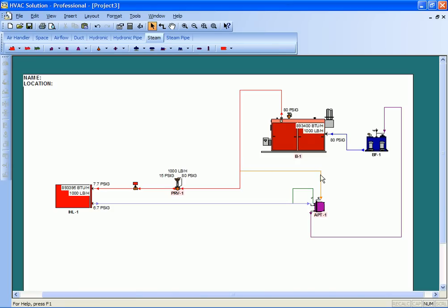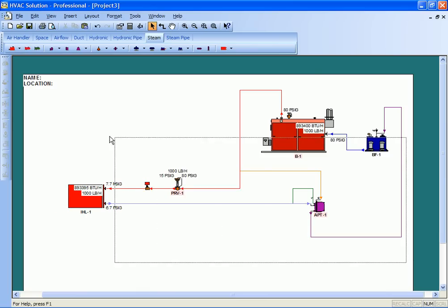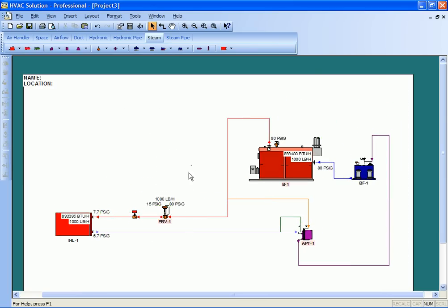So here we just take that 100 psi or say 80 psi steam, use that to power whatever condensate we're coming back, and now this system will function correctly. It won't have any problems because the condensate can't build up, because we actually have some other source pushing the steam back to the system.